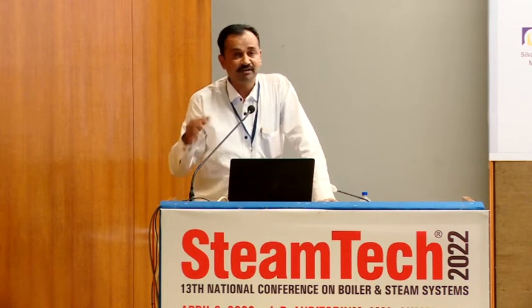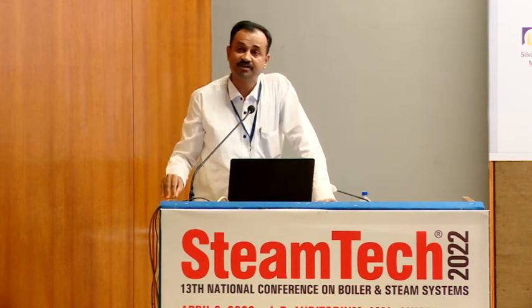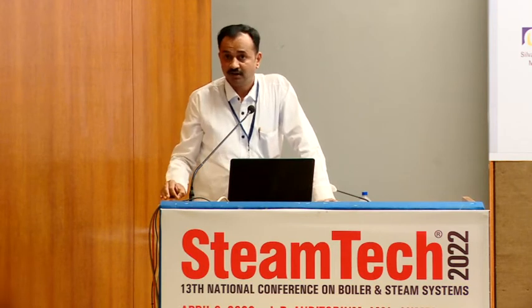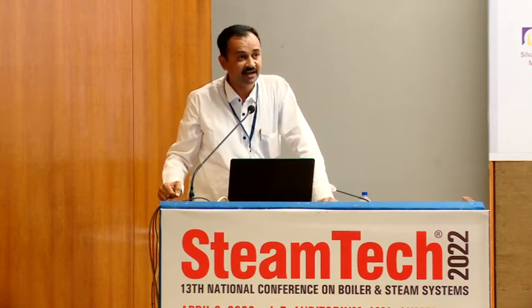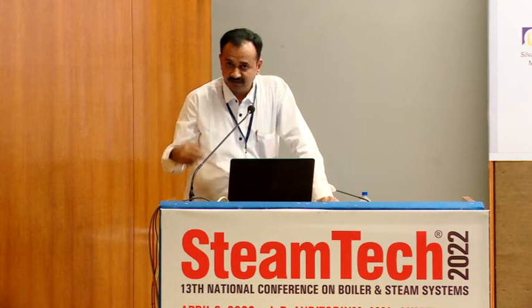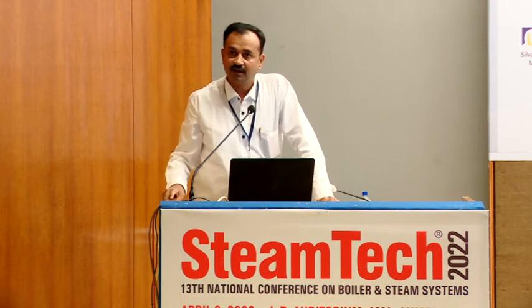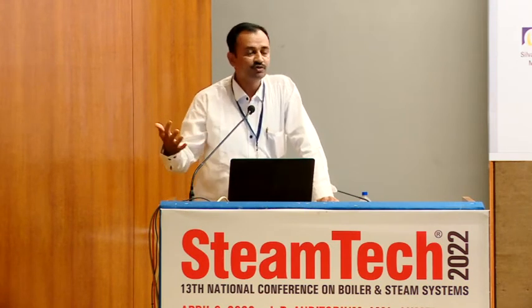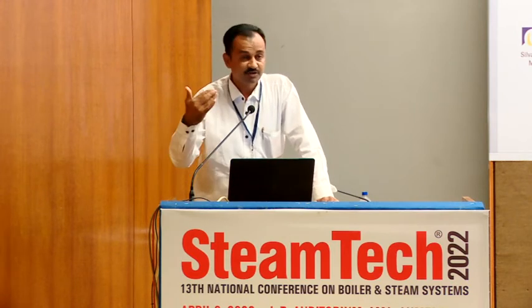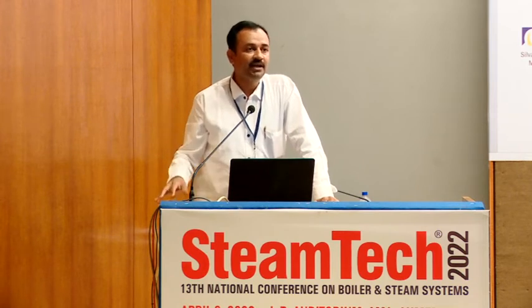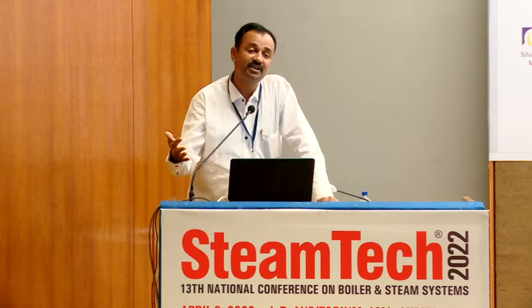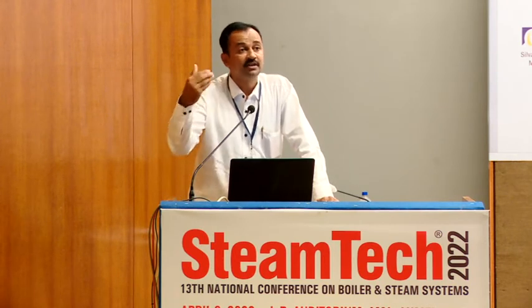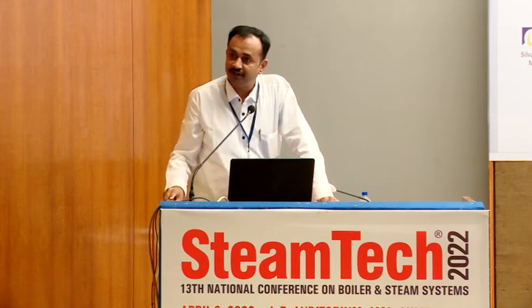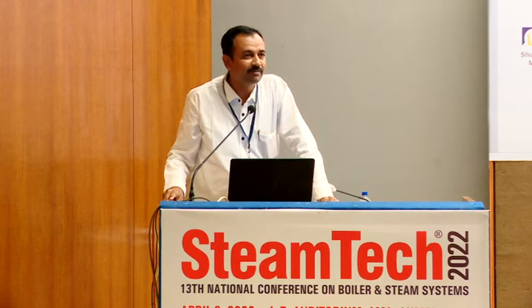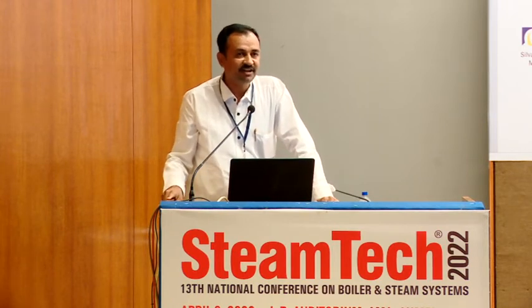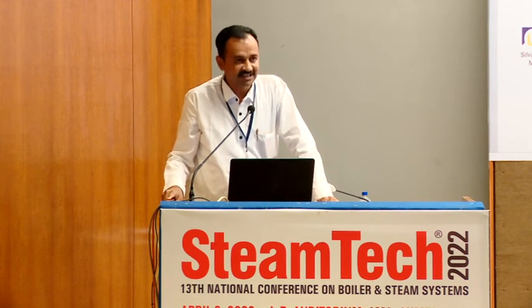From the report we derive a four-quadrant identification. First, real-time monitoring, where the boiler operator and user can connect immediately if there is any unsafe mishap or draft pressure going out of range, and see what can be done. If steam generation is getting reduced due to some imbalance of the parameters, what can be done. So these are the real-time suggestions. Secondly, every weekly report can give you the idea of what further fine-tuning of the parameters is feasible. Likewise, the boiler is not running at the rated pressure, or the feed water temperature was earlier slightly higher but currently is not at that level. So these are the actions we can suggest and trigger, the corrective actions needed to sustain these parameters.